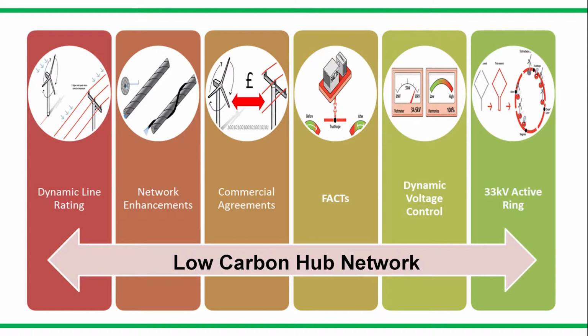We're fitting a large FACTS device, a STATCOM at 33 kV. It's a 3.75 MVAR unit, and this will be the first time it's been used in this way on a 33 kV network to absorb reactive power in order to reduce the effect of voltage rise during minimum load, maximum generation conditions, put at the weakest point on a network where it will have the maximum use.